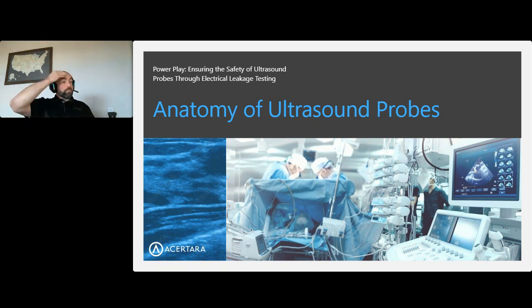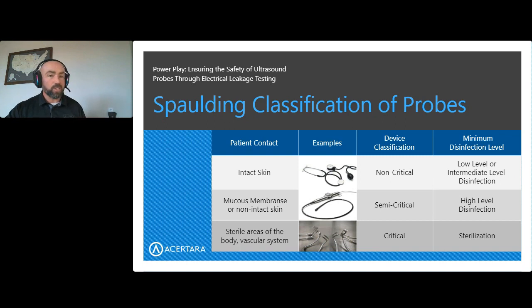So how do you decide how the ultrasound probe will be disinfected? That's great. The IFU is definitely where we want to focus our time, but you can obviously use the Spaulding classification of probes to be able to understand how that actually happens. So on intact skin, device classification is non-critical. I would say GE probes fall into that category as well. So most general use probes are going to fall into that category for cardiology, vascular, radiology, and musculoskeletal imaging. Those are all going to be low-level disinfection, although people still do high-level disinfection on them, even though they don't need to.